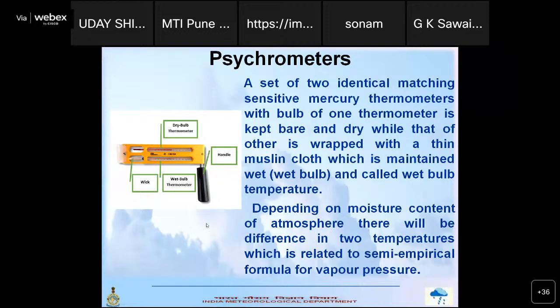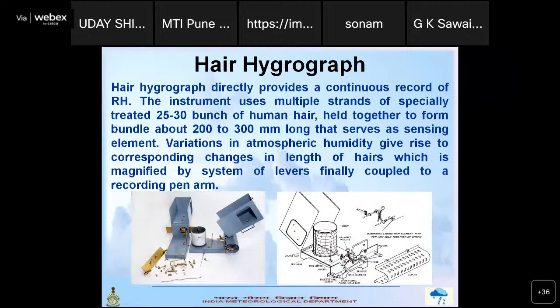Besides that, there is also a hygrograph, the hair hygrograph, which is also a traditional way to measure humidity. This instrument is manufactured in our workshop in Pune division as well. This is the measurement of humidity with human hair. Human hair has a property to elongate, increasing in length when the humidity is more. When humidity is less, the human hair will contract.